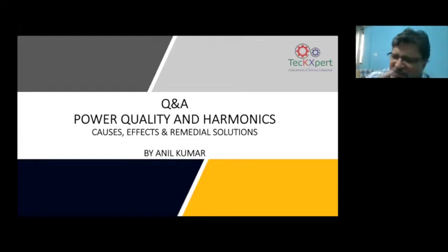If the grounding is not proper, certainly there will be an impact on the ground from the harmonics flowing on the neutral or on the other phases. That is one part. The second part is the higher frequency current that flows in the phase and in the neutral through the capacitive and inductive impedance, which can reflect on the ground system and then create a ground current and a ground voltage. Now, if your sensitive electronics fails due to this ground voltage, then the answer lies there. It depends on the sensitivity of that electronics and how important that electronic device is in the system.